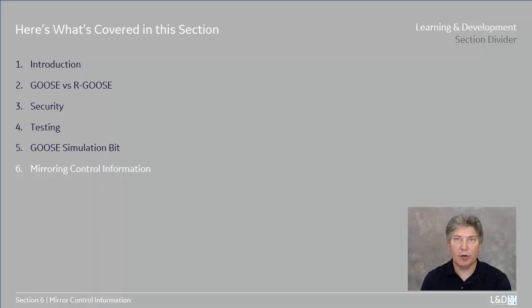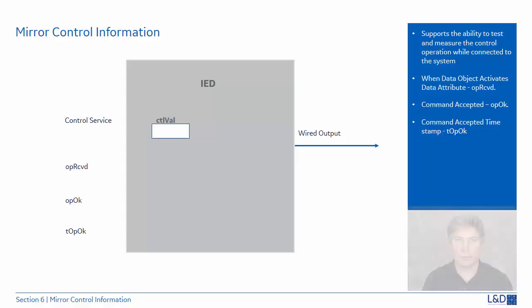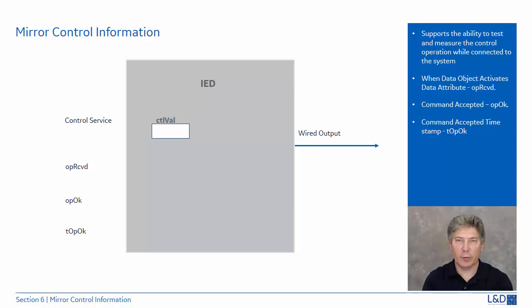In this section, we'll take a look at mirroring control information used for commissioning and testing purposes. The feature of mirroring of control information was added to IEC 61850 Edition 2. This supports the possibility to test and measure the performance of a control operation while the device is connected to the system. Let's follow through the steps.